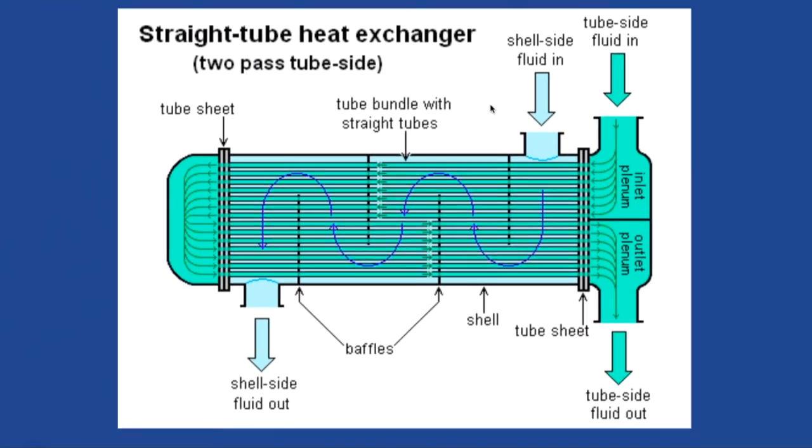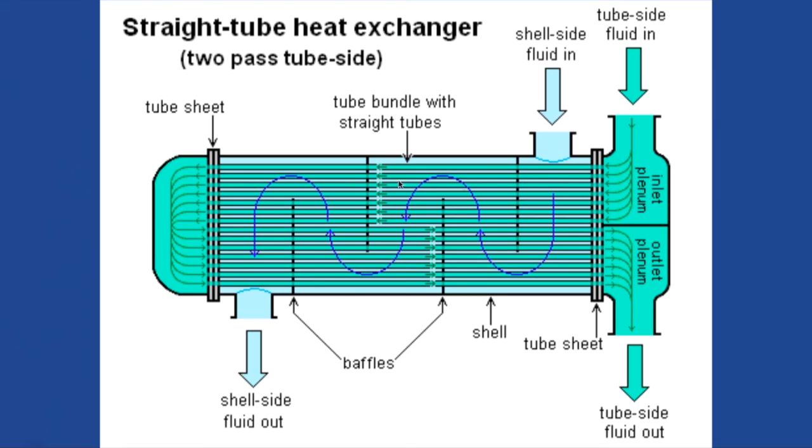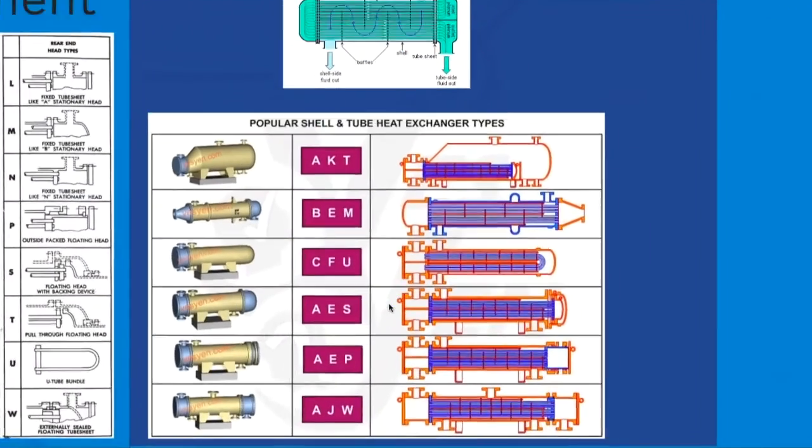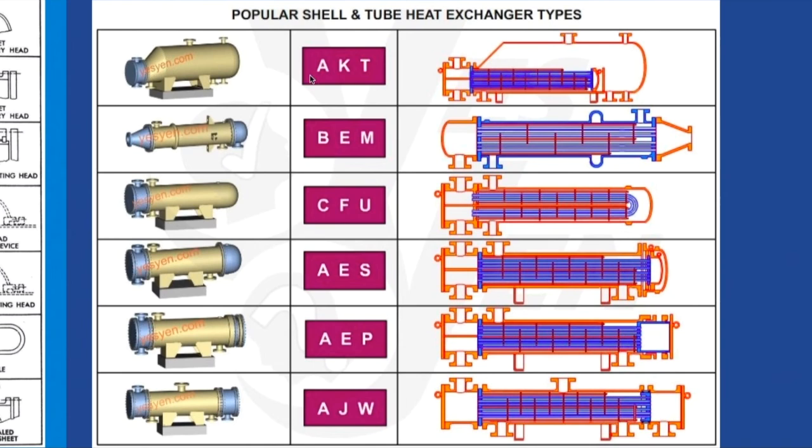Fluid goes in, transfers heat, and goes out. Looking at different configurations: this is A-K-T configuration—A for this piece, K for this section, and T because there's no extra component. This type is also used for evaporation, allowing gases to form here. There's also B-E-M and other configurations with different shells.